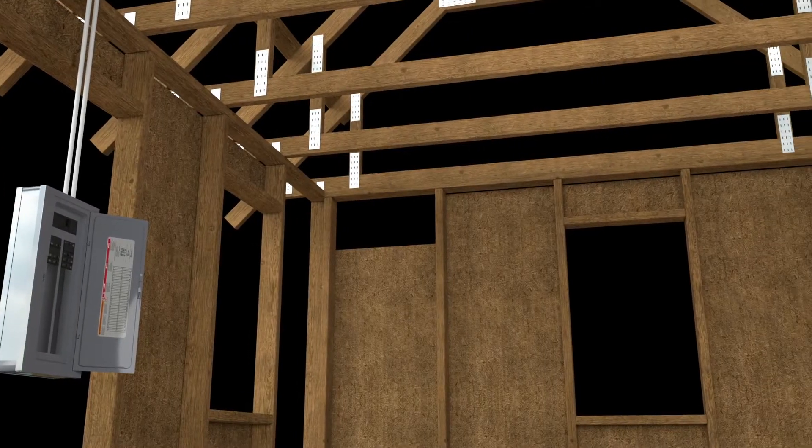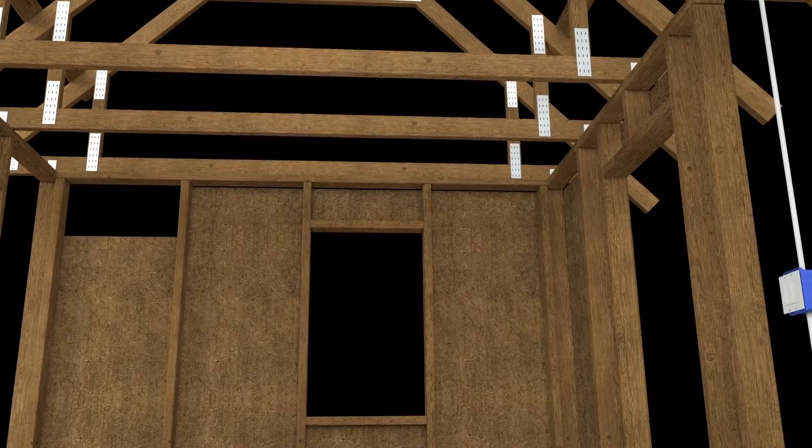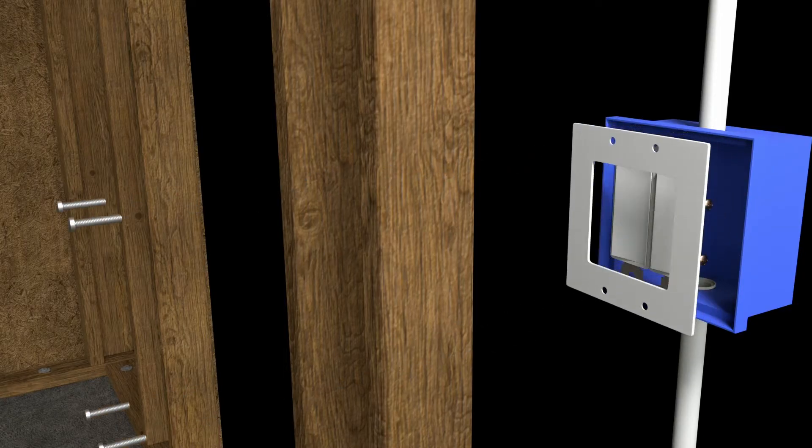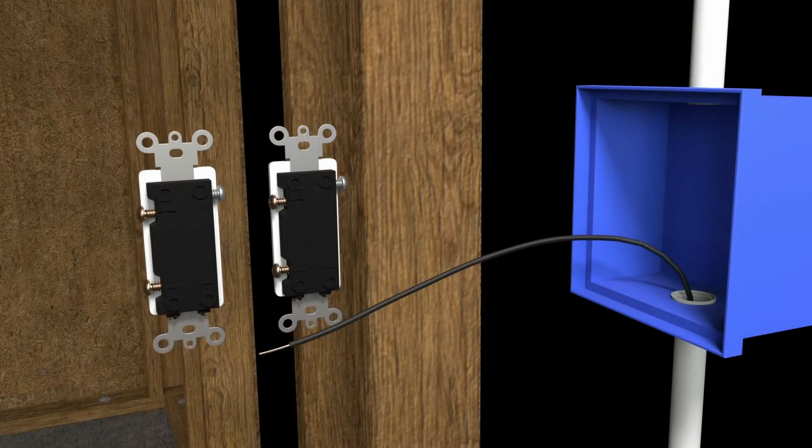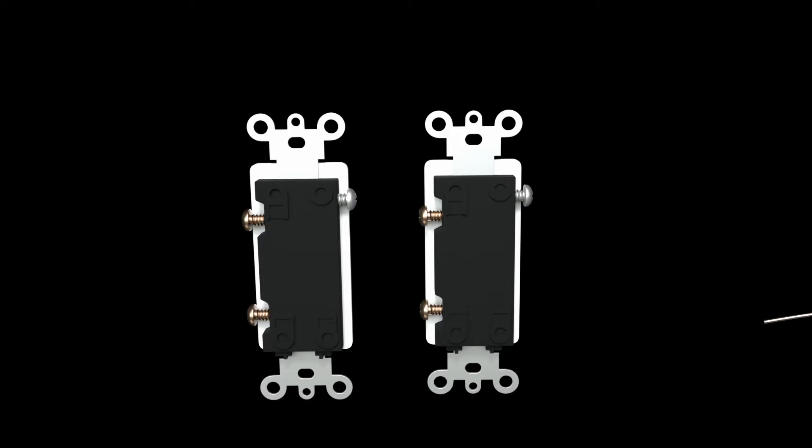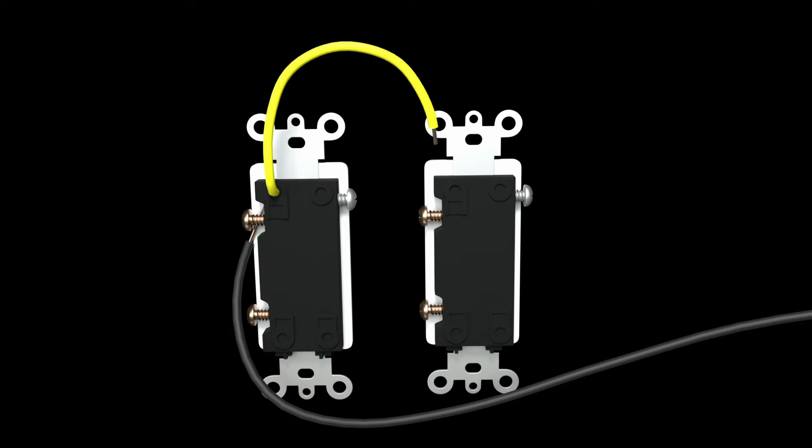We bring a single 20 amp branch circuit from the electrical panel to two wall switches. At the wall switches we attach the power conductor to the line side of a single pole switch. Then add a jumper wire from the powered switch to the second switch.